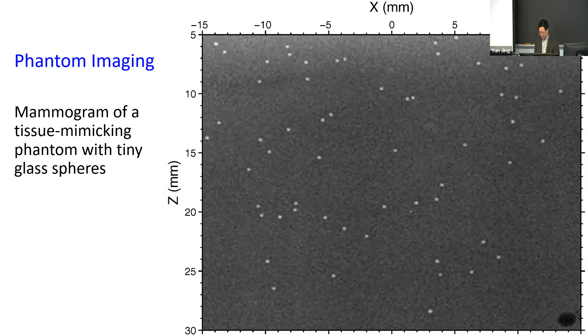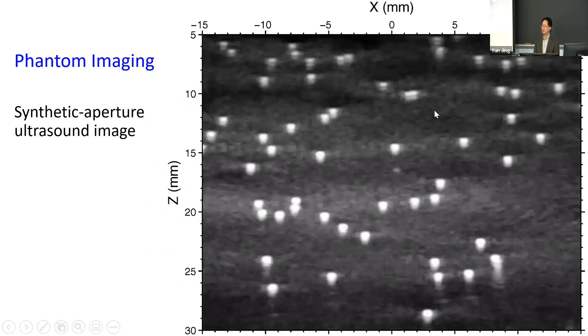And this is the phantom scanned using a mammogram machine. You can see all these cross-shaped white spots here. And this is using our synthetic aperture ultrasound machine to scan the image. You can see that the resolution is much lower. For example, here there are 2 of them, right? As I mentioned earlier, it's very important to count how many microcalcifications there are, because if within 1 cc you can detect a cluster, it becomes suspicious, and then you need further diagnosis. In this machine, you can only see 1, right? And in fact there are 2, and so on. That's why resolution is very important.